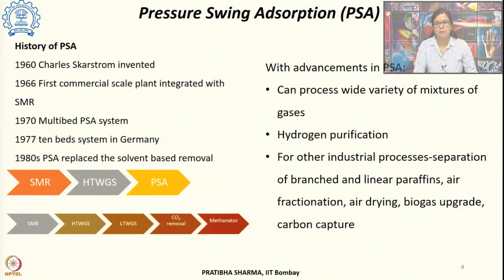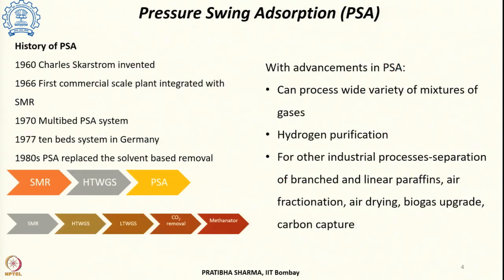The first method, which is most widely used for hydrogen purification, is pressure swing adsorption. In this method, we can get ultra-pure hydrogen — 99.99+ percent purity can be achieved. With modern pressure swing adsorption plants, even 90% hydrogen recovery could be achieved.